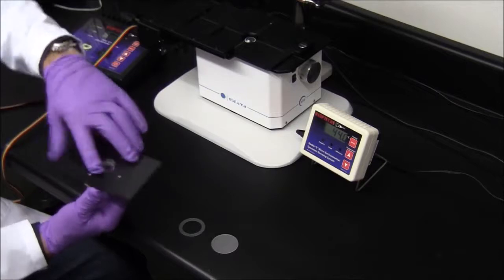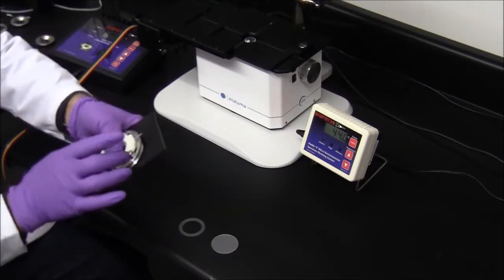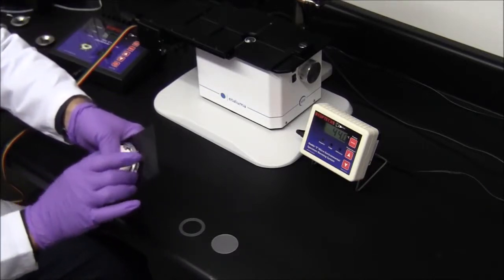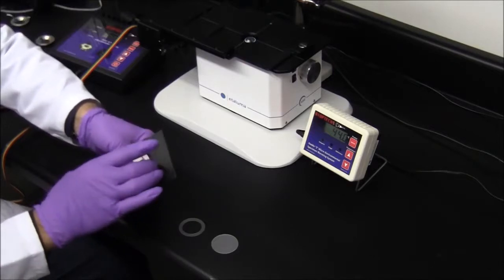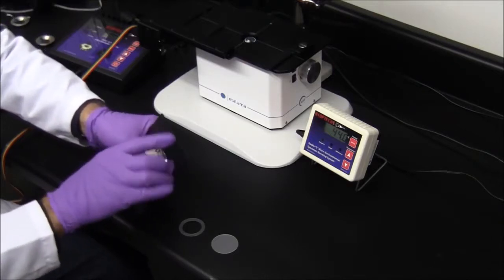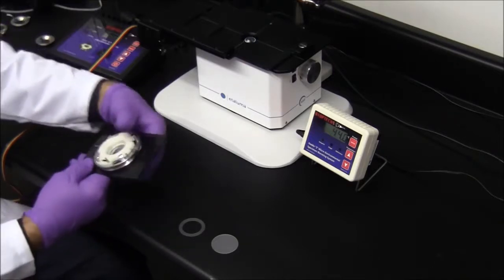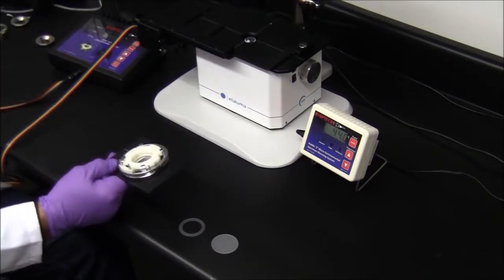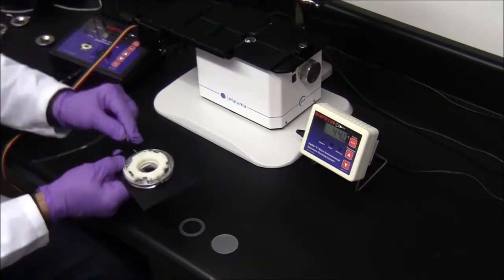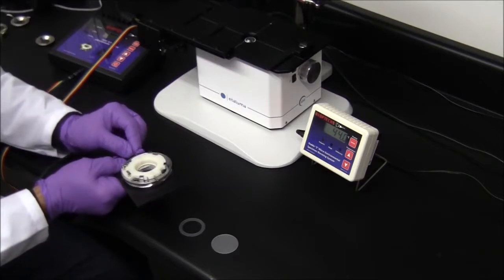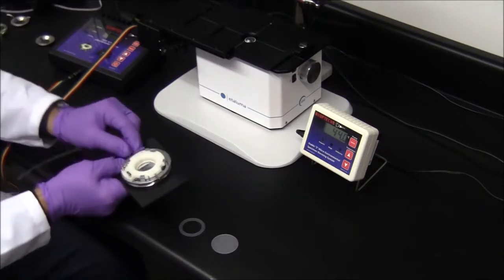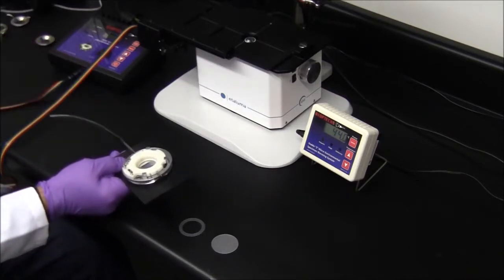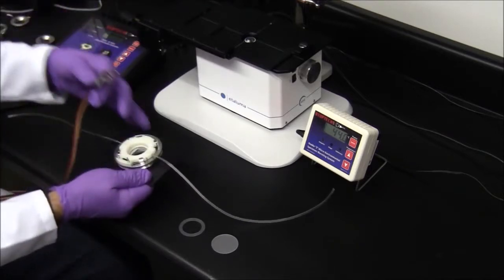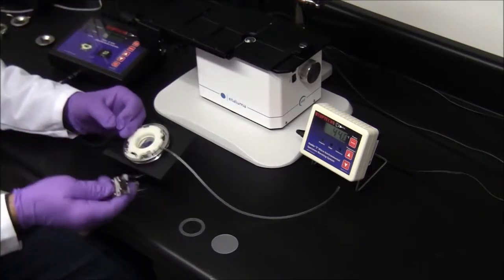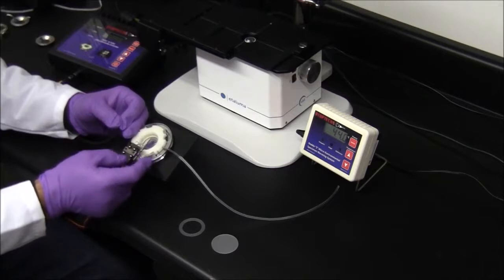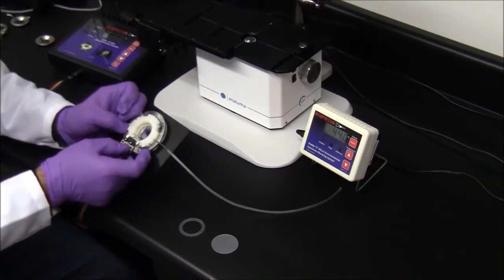To seal the chamber, simply turn it over and rotate the outer knurled ring to secure all the components. Perfusion lines are attached for supply and outflow. Under normal circumstances, these lines would already be attached to a source and drain. Next, an electrical connector is locked in place that carries both power and sensor information to the controller.